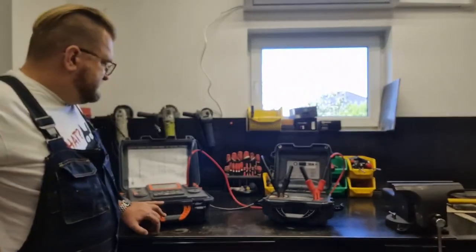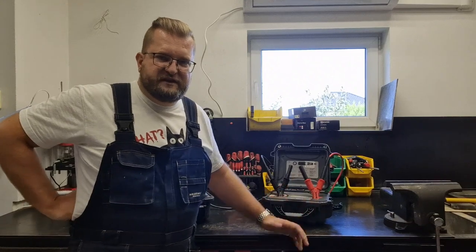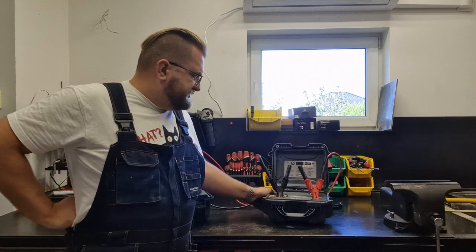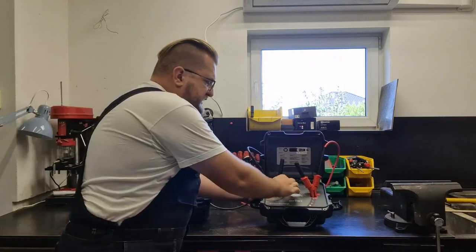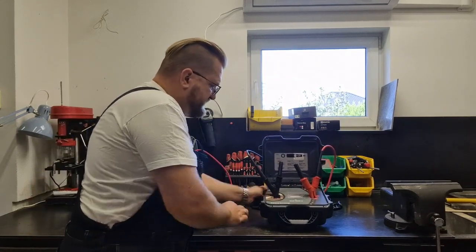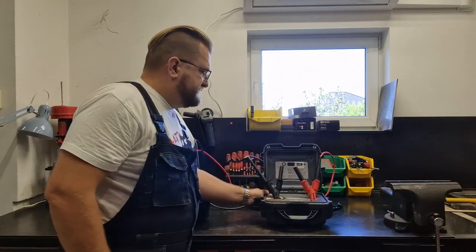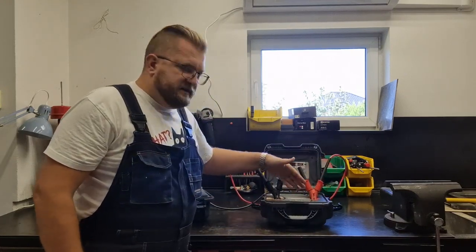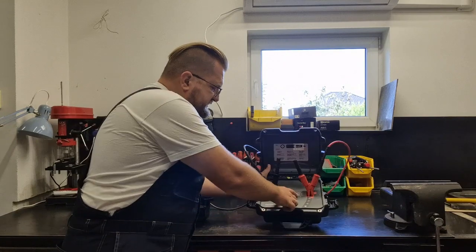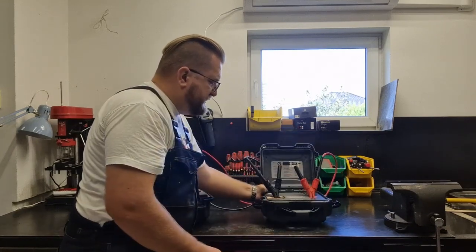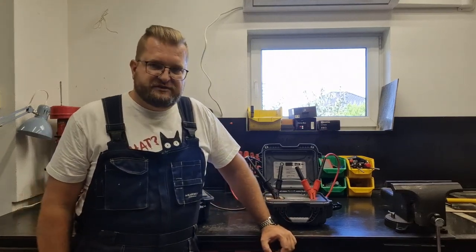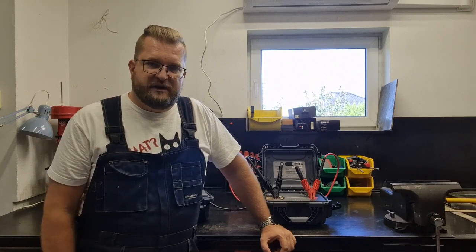But to show this, I do not have a proper cable with some failure inside, so I will use the partial discharge simulator. So this is a cross section of the cable, and we connect the minus to the main core and plus to the shield, and inside there is a structure which simulates the partial discharge. Over here is also a place where there will be visualization of the partial discharge by a diode blinking.